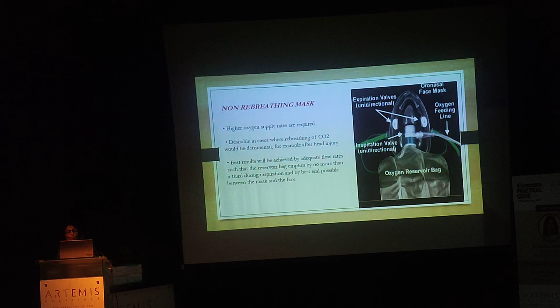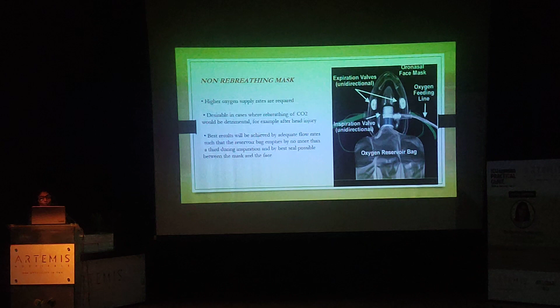The best results will be achieved by an adequate flow rate such that the reservoir bag empties by no more than a third during inspiration, and the best seal possible between the mask and the face. There should not be any leakage.